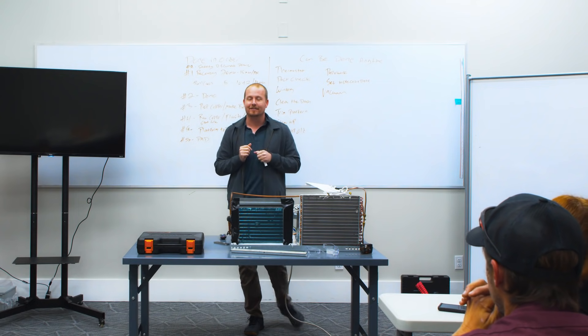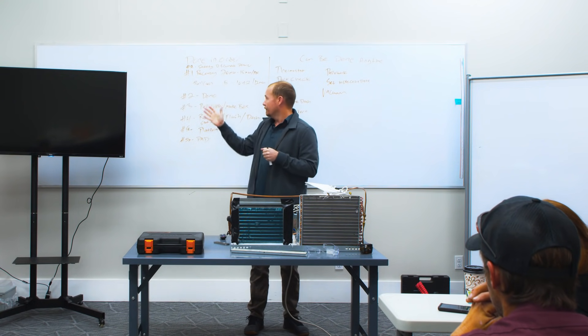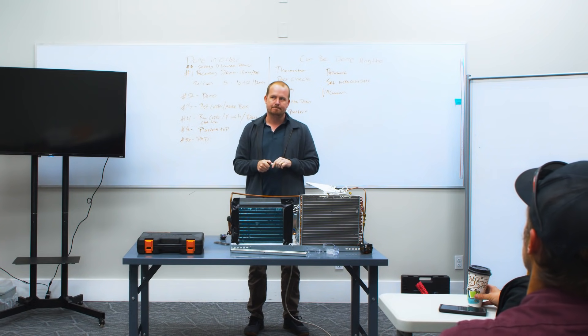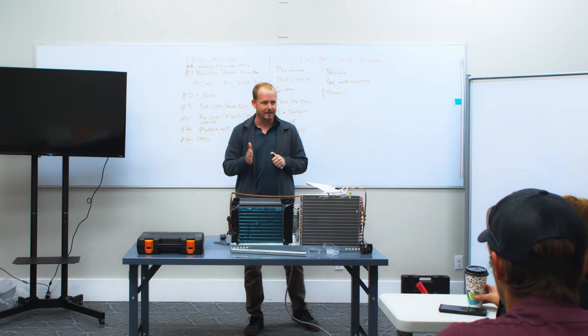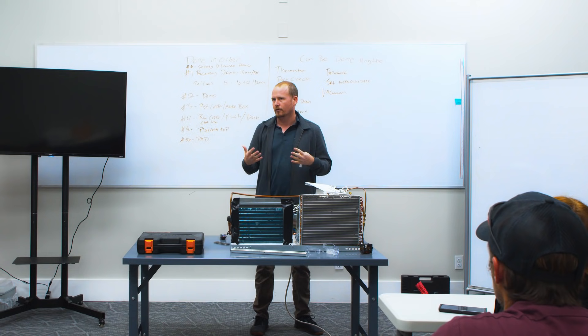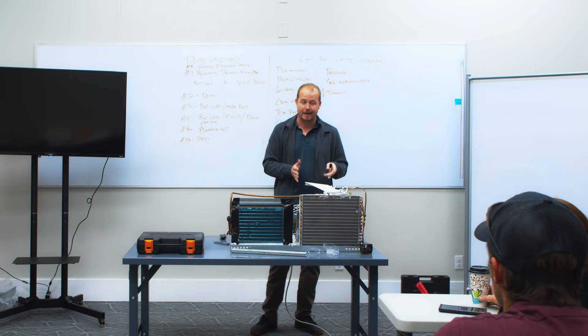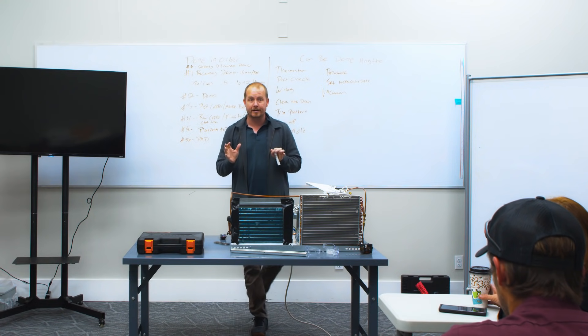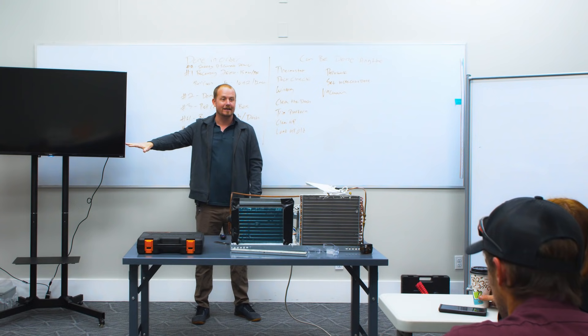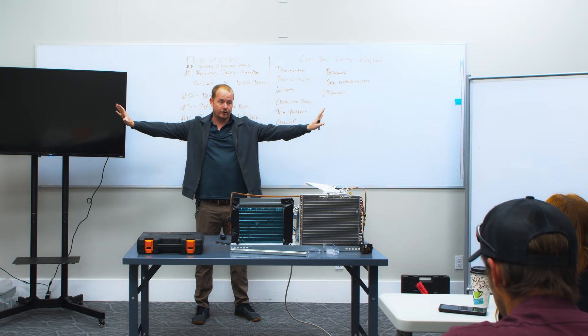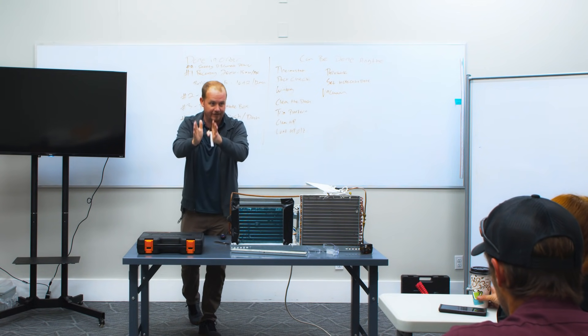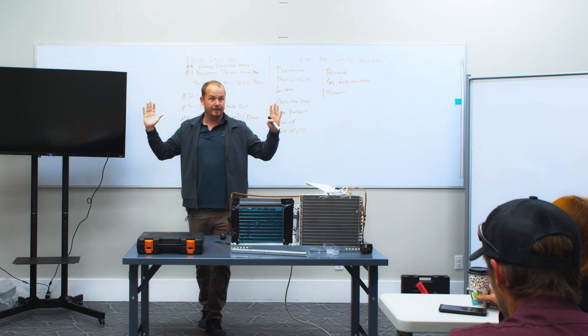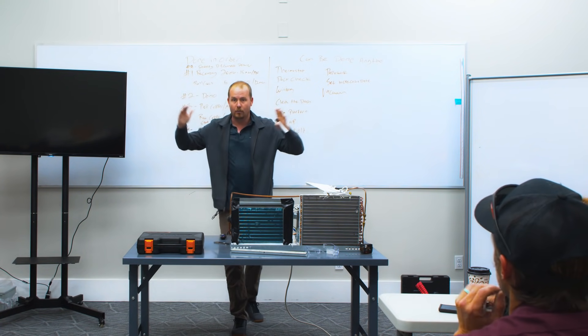If we do this better, it doesn't have to be so panicky, exhausting, or stressful. You've all been on jobs where they just go smooth and it doesn't feel like you're working that hard — that's the goal for all of us regardless of what segment of the business you're in. If you're a service tech, you'll do evaporators, compressors, maintenances, clean drains — all process-oriented things. But when you get into troubleshooting, scrap that mindset. Go wide, take your time assessing everything, then go narrow to the problem, fix it, then go wide again to make sure you didn't miss anything. Troubleshooting is wide-narrow-wide; projects are narrow-narrow-narrow with a little wide at the end.